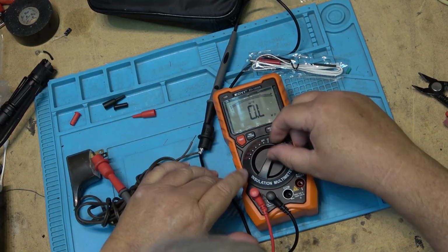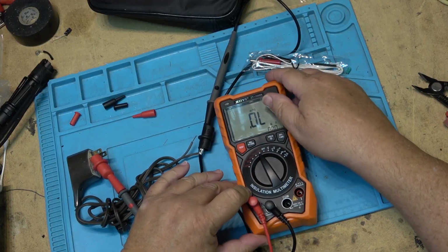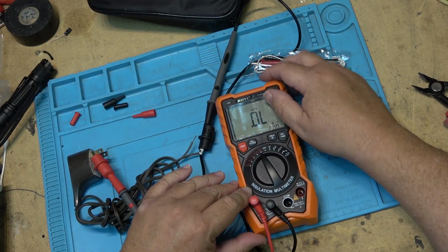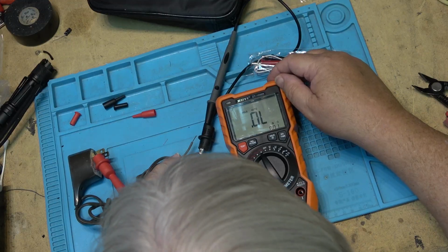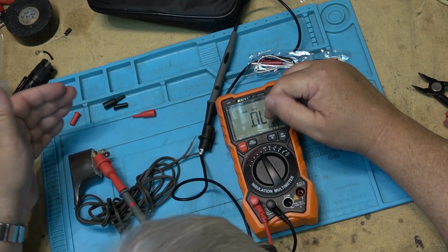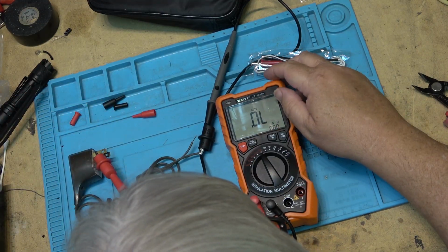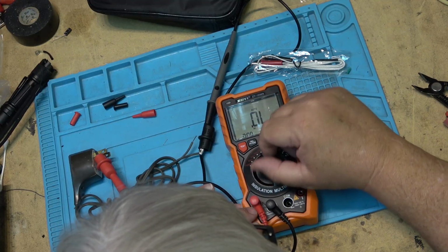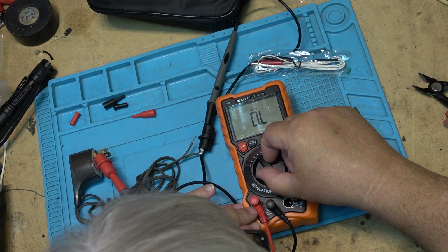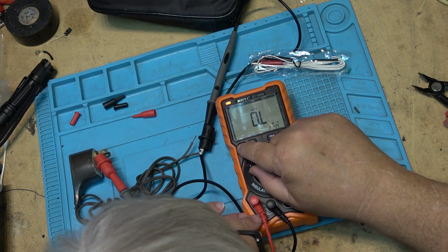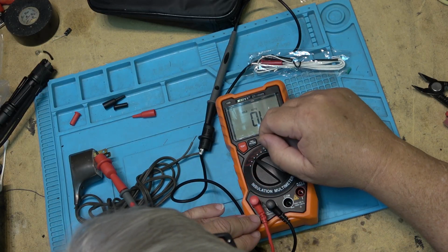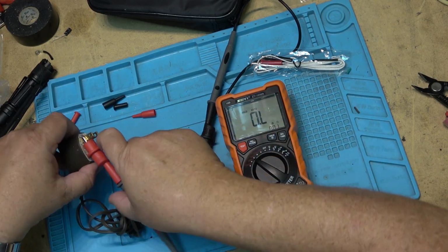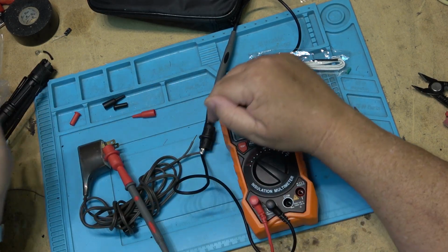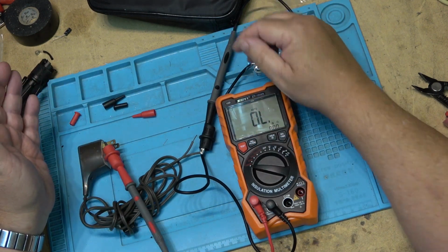And now I can proceed to do the insulation breakdown test. Press the test button. It will send a voltage down and see if there's any leakage between the two. And if there is any, we'll be able to detect it here. And I can progressively increase the voltage between the two to see if there's any short. Now, for example, if I were to place a short here, we would see it. I can take this up as high as 1,000 volts.